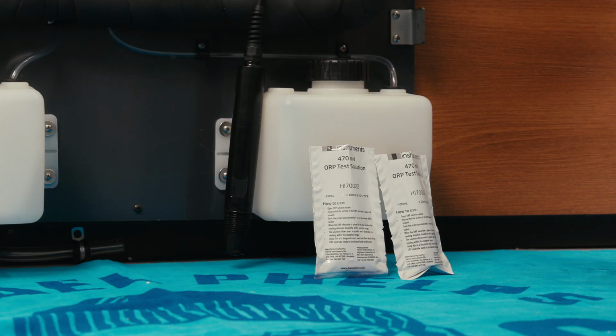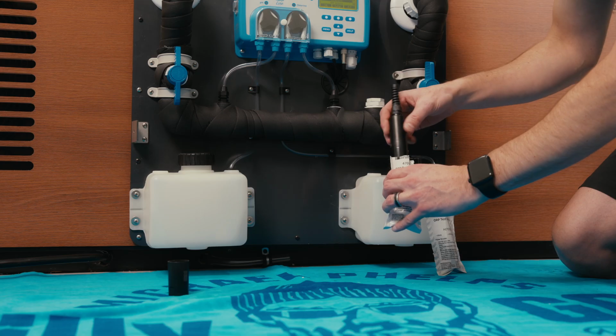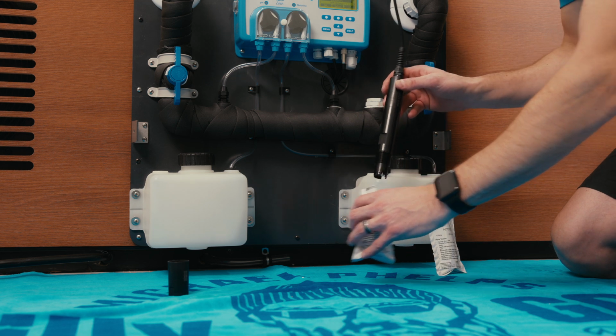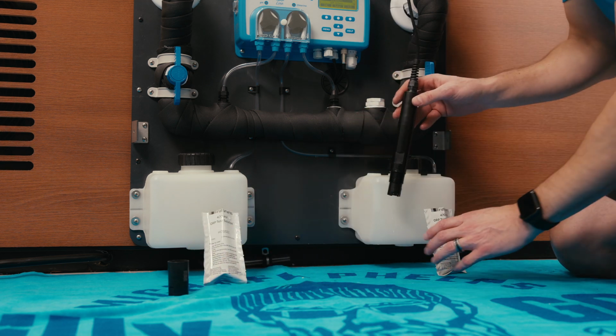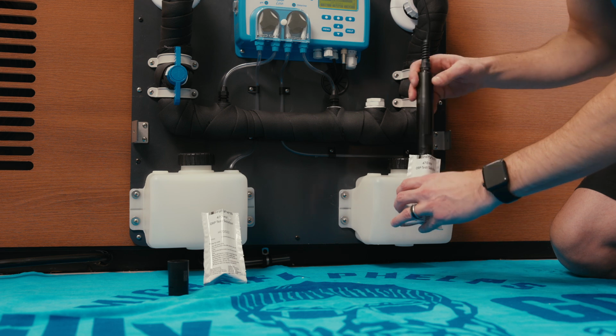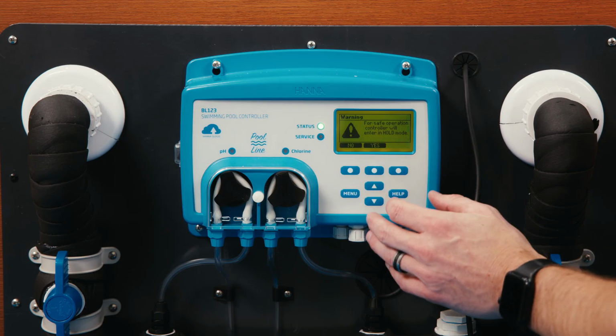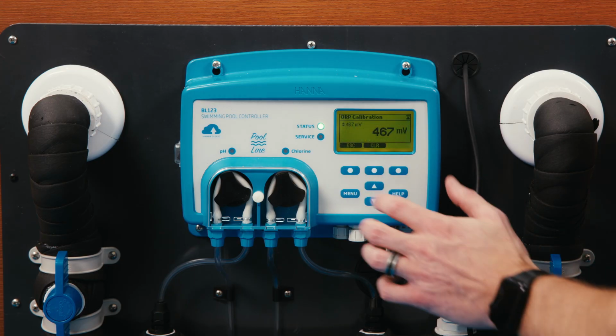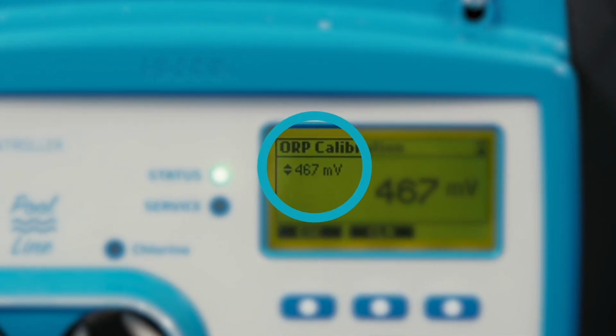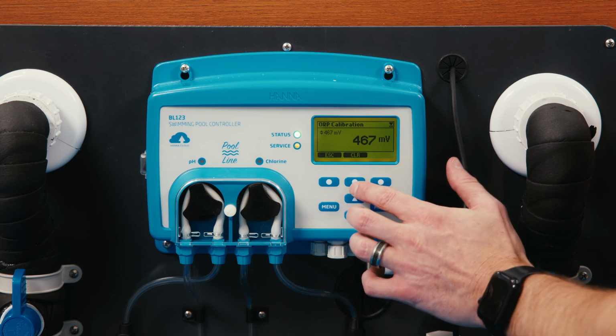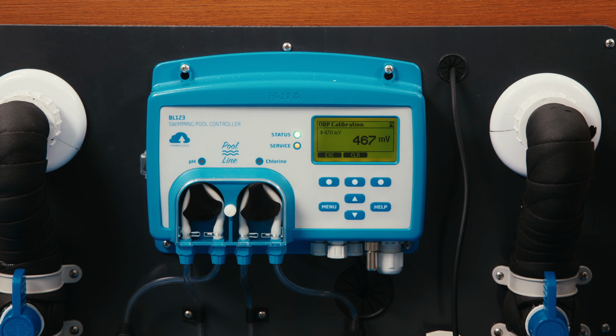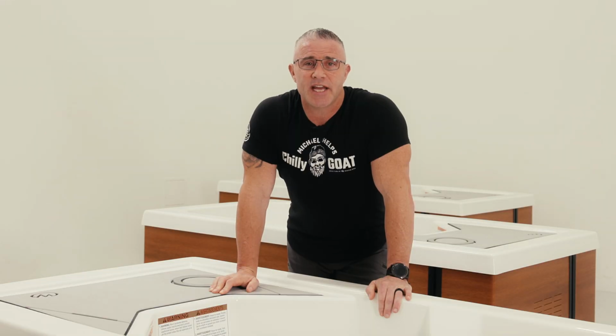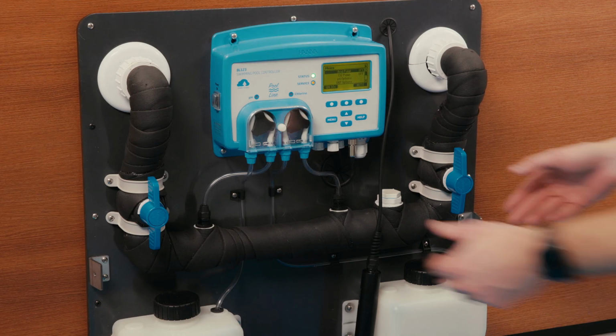Your kit includes two ORP solution packets. Use this first packet to rinse and clean the probe, then move the probe into the second packet and let it rest on a stable surface. On the controller, start ORP calibration, then ensure that your set point reads 470 millivolts. If it does not, use the up and down arrows to adjust accordingly and wait for the reading to stabilize, then confirm. When both pH and ORP calibrations are complete, close the two valves again.